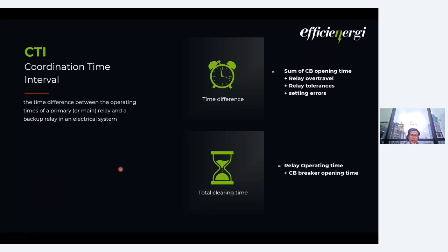Again, the relay tolerances. If you go deeper into the manufacturer's data sheet, you will always see a plus minus tolerance on the curve. But in an ETAP study, you will never see minimum and maximum given on the curves. It is always a theoretical value. But that plus minus 5% also we have to consider. We'll go deeper into this when we have the session on how to coordinate between relays.